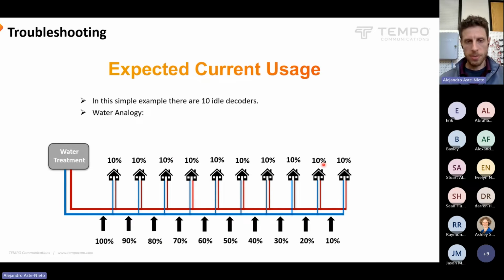2 wires here, so you can think of it in terms of any water being consumed by this house also coming back through the sewer. So you take a measurement here on the water main or the sewer, and the sewer is going to have a lot more water flowing through here at the beginning of the street also. And if you clamp around both wires, how much water is coming and going at the same time, it's going to average that out to 0. So I like to think of it in terms of water main and sewer line to reflect that there's 2 wires going on.